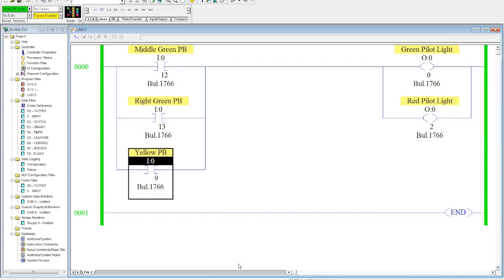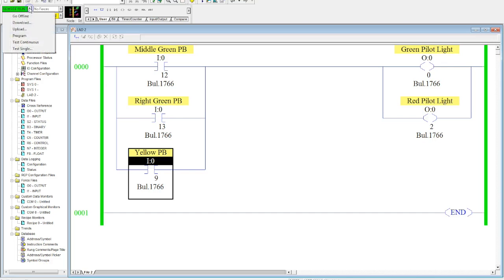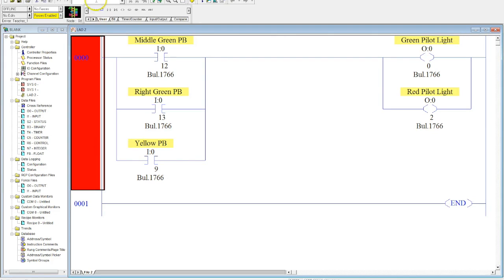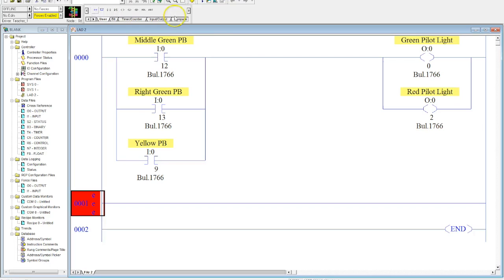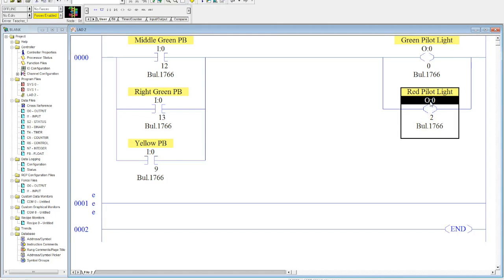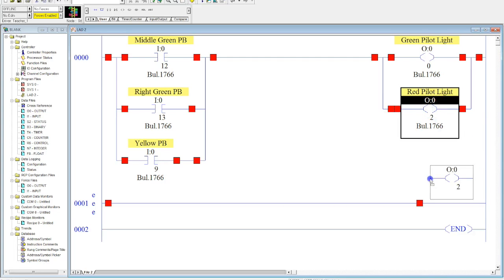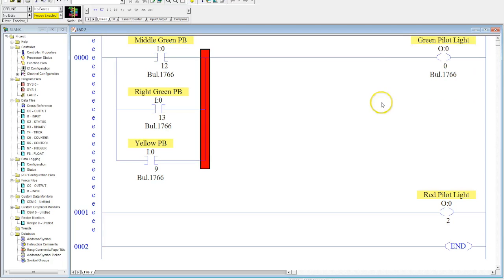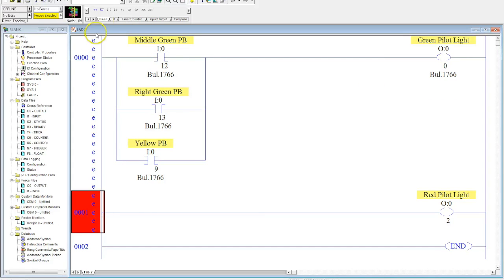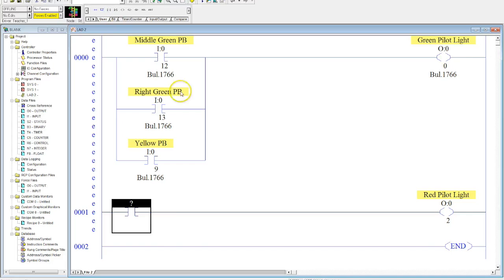Now that we know our program works, let me show you how I personally prefer to put all of my outputs in a RSLogix 500 program. So, I'm going to go offline here, and this is how I do. I only personally like to have a single output on every single rung. So, I'm going to come in here, and I'm going to add a rung. And then what I'm going to do is I'm going to grab the entire output and move it down to my rung one. So, I'm going to take my red pilot light. I'm going to grab it. Now, don't grab the address if you're trying to move the whole thing. I'm going to grab this here, drag it down, drop it right there. I'm going to delete. I click on the corner here. I'm going to delete that parallel branch.